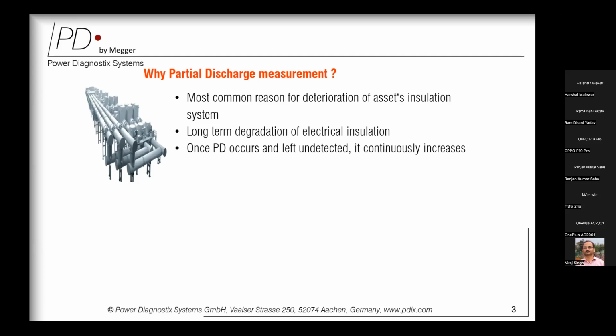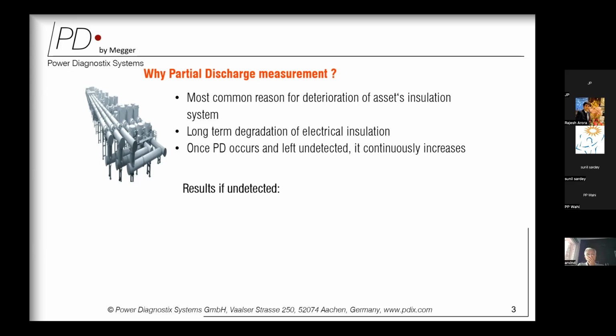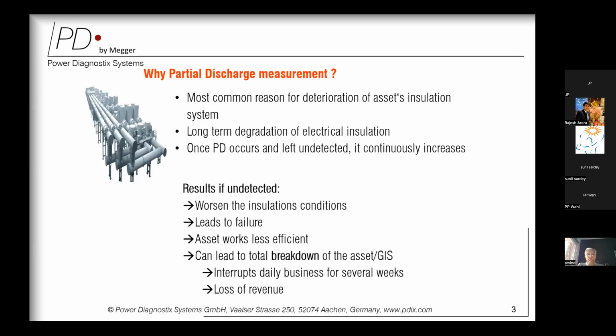So these are the reasons contributing to the fact that some measurement is required for this phenomenon called partial discharge. If it is undetected or not measured, it will worsen the insulation condition, which will lead to failure or the asset working less efficiently, and can lead to a total breakdown of the asset, which is GIS in this case. That could disturb our daily operations for several weeks or days, and it is directly associated with loss of revenue. So these are the most common facts and reasons why partial discharge measurement is of utmost importance in GIS.